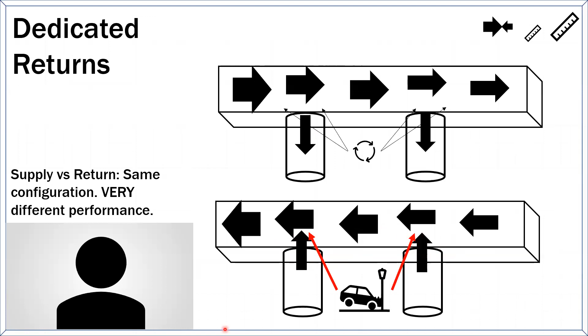That having been said, on a return system, whether it's round or rectangle, if you make your return look like this, it's going to be more restrictive, particularly when you bring bigger amounts of air into that air volume. If this is a bigger air volume than this, it won't resist as much, because this will push its way in and just pull the air around. But if this is a smaller air volume going in, the less it disrupts the flow of air. The bigger the air volume going in, the more it disrupts the flow.